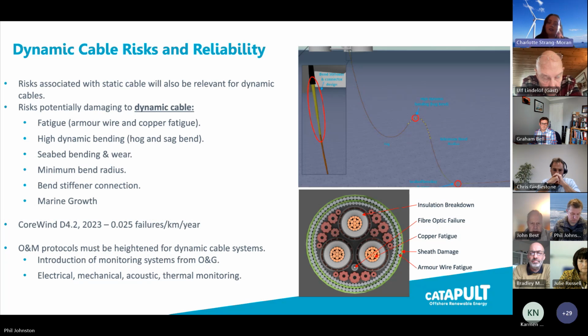High dynamic bending can cause issues at the hog and sag bend of your dynamic configuration as well. Seabed bending and wear can also be an issue, along with abrasion. And minimum bend radius can be surpassed as an issue during operation, as well as through installation, that is more commonly seen for static, but is also seen for dynamic cables. We also have to be aware that from oil and gas, there are failures around bend stiffener connectors as well.